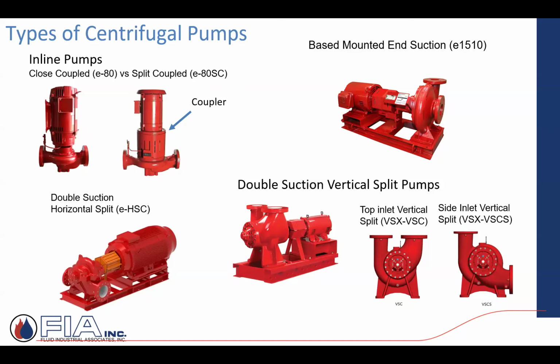A close coupled motor shaft connected through seals directly to an impeller that's sitting inside the volute, close coupled. A larger, same family, if you will, a vertical inline, but a split coupled. Because as you get into some of these bigger inline pumps, they'll actually come with like a foot base, a foot mounting, so that you can support this pump, this volute part of the pump, because as you get into the higher capacities, say it again.